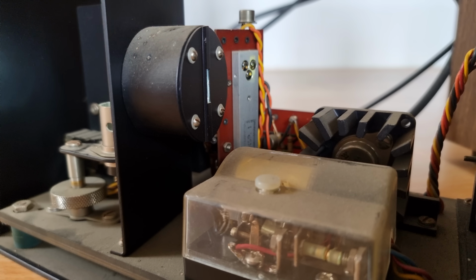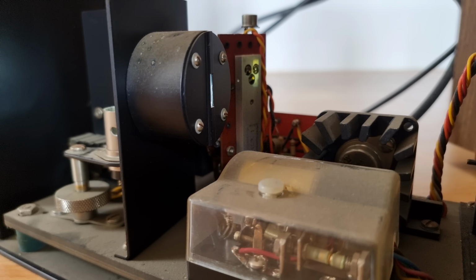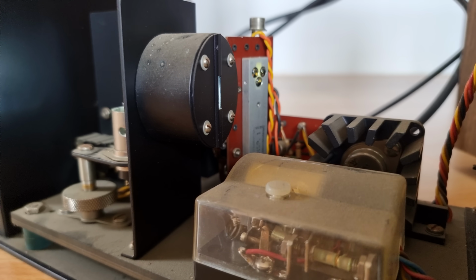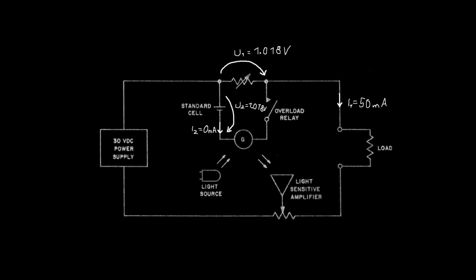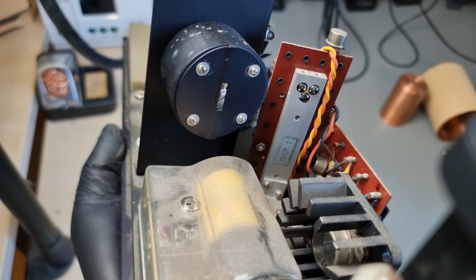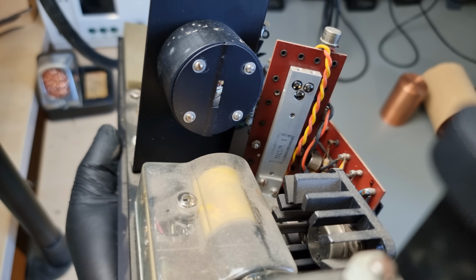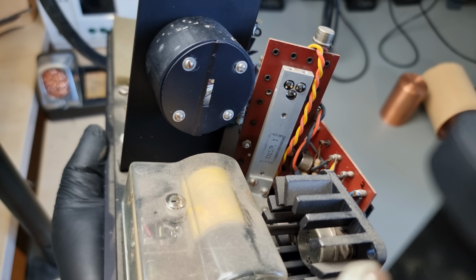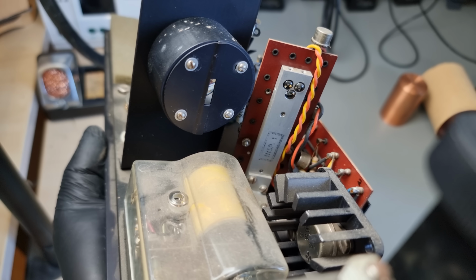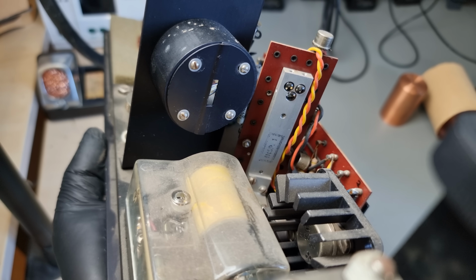If one gets illuminated more than the other, a light-sensitive amplifier steps in, acting like a variable resistance, trying to recenter the beam by steering the current back to 50 mA. The central lower phototransistor should always be illuminated. When the beam is centered, the control loop is stabilized, and the zero Weston cell current condition can be ensured.